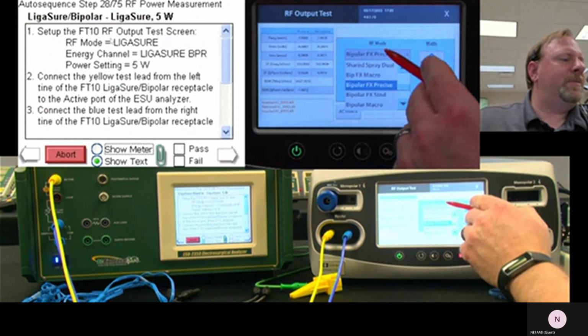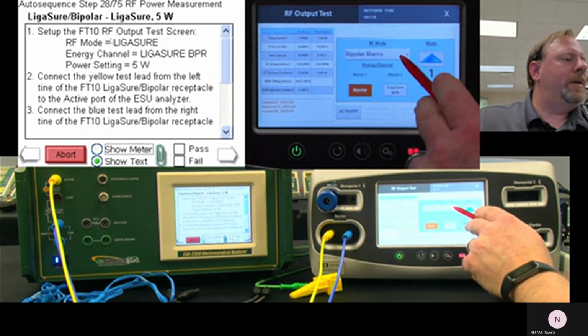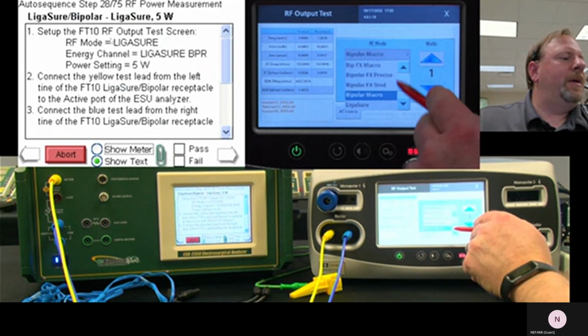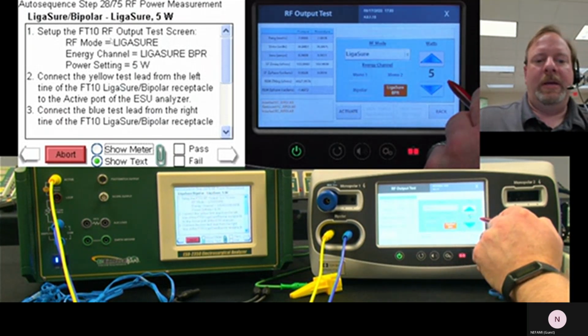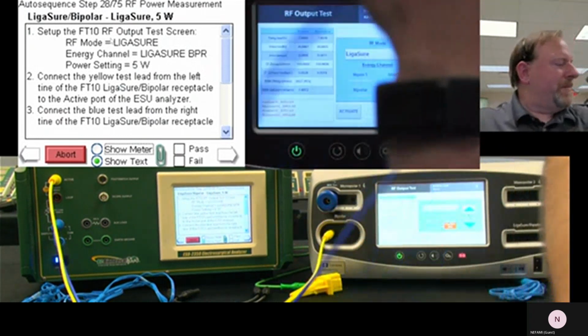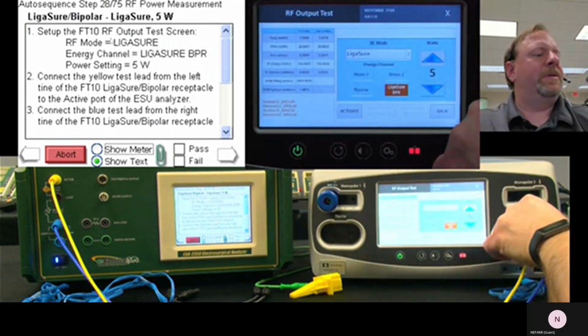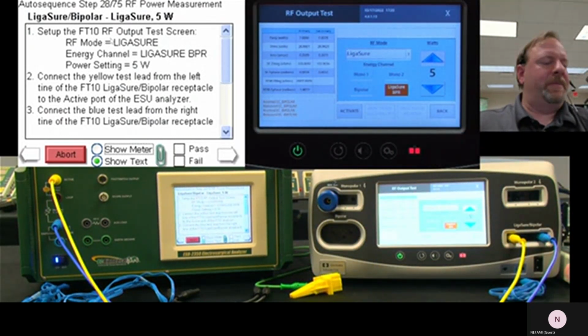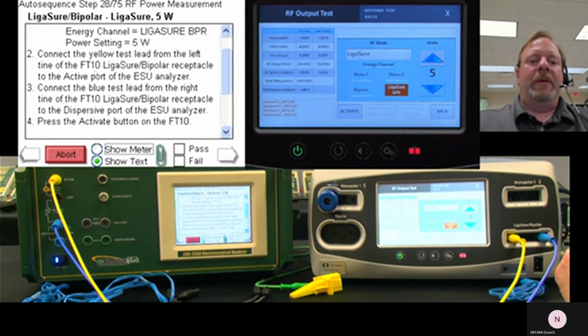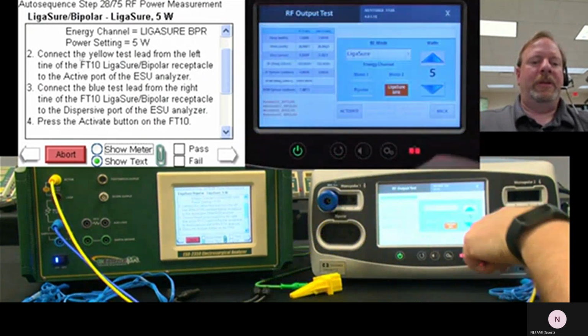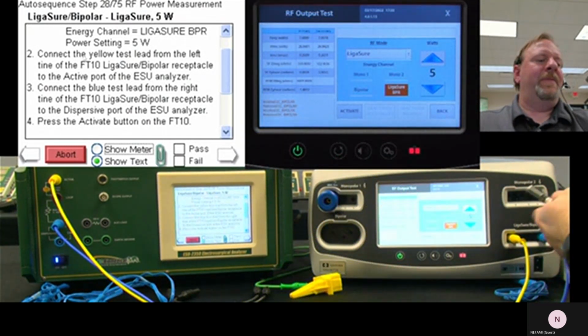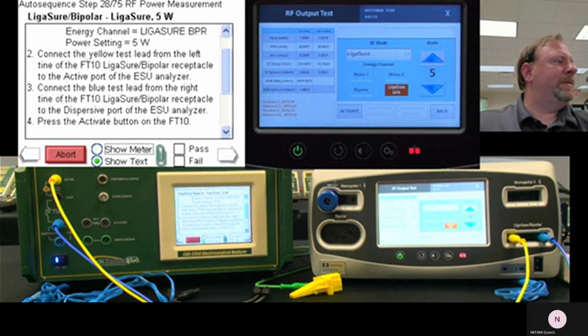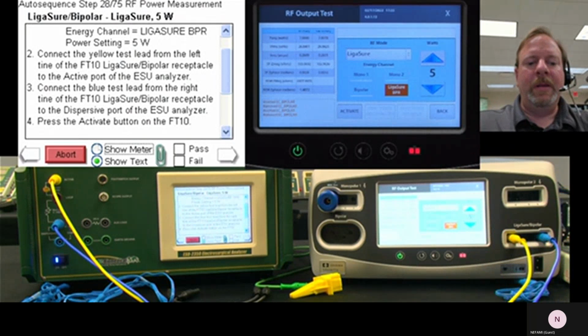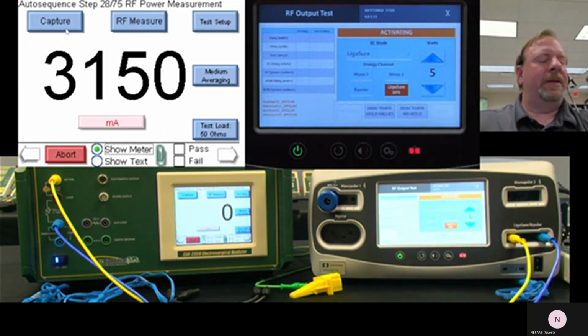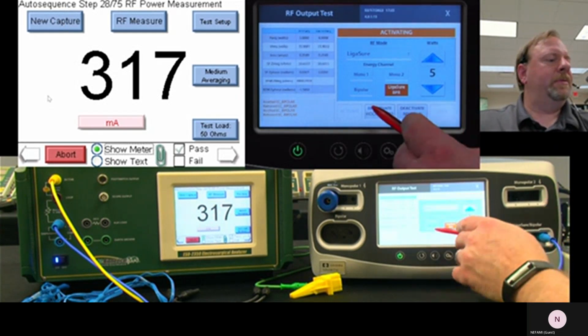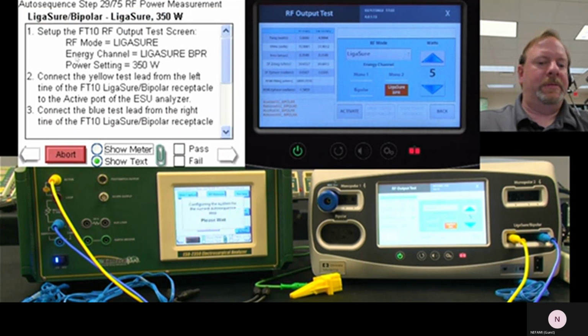LigaSure. Okay, that's one question I get: how do we test LigaSure? Well, number one, you want to be in this test mode, and you want to push the right button correctly. And 5 watts. So LigaSure is just like bipolar. As far as the 2350 is concerned, it doesn't know the difference. It's just measuring a signal. So we follow the connections here, active to the left tine, blue to the right tine. Does it really matter if I reverse these? No. But for consistency, we just do it this way. So we got 5 watts, we activate, and we capture, deactivate. This time we're at 50 ohms.